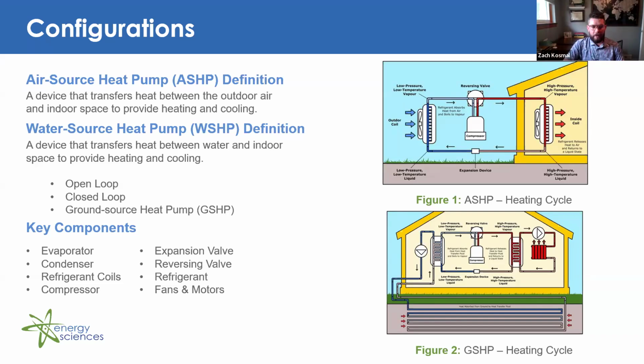The water is typically a water antifreeze solution to reduce any freezing in that system. So in summary, a closed loop system maintains a stable internal pressure, and it requires less pump energy by recirculating that water antifreeze solution. So another version of a water source heat pump may be a ground source heat pump. And you can see there in figure 2, that is an example of a ground source heat pump in which the piping is laid horizontally in that figure.